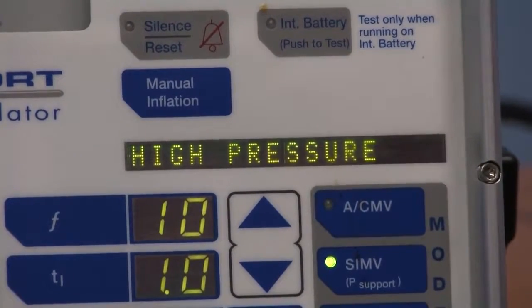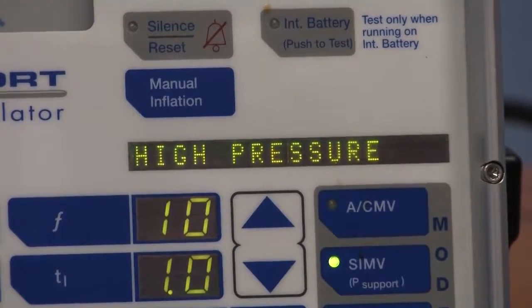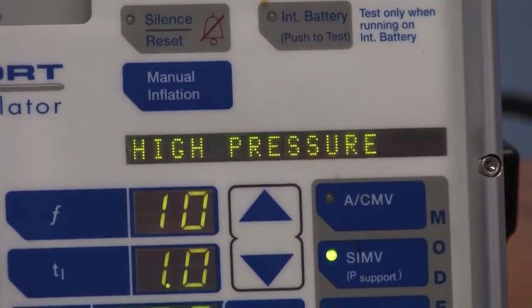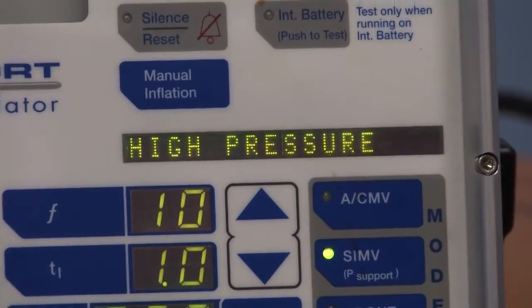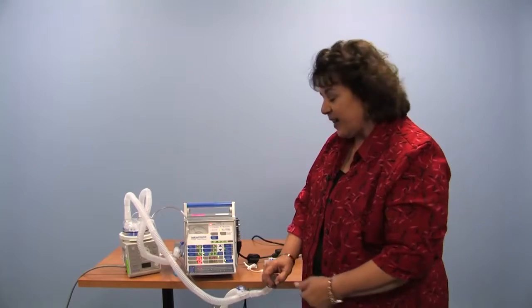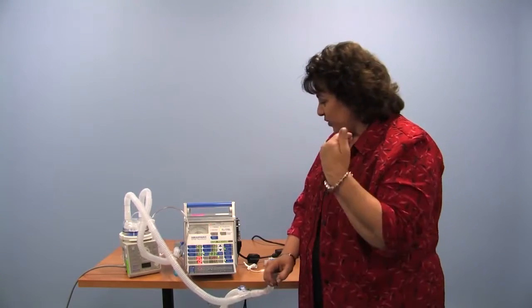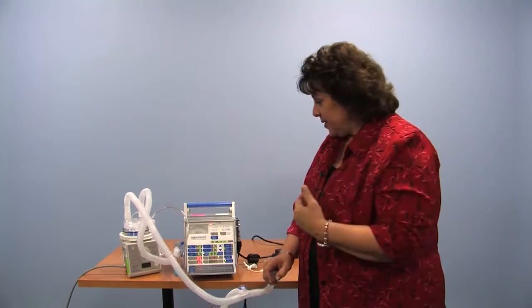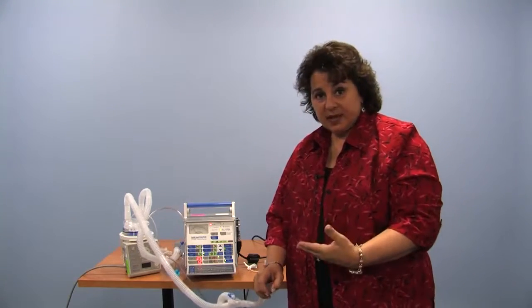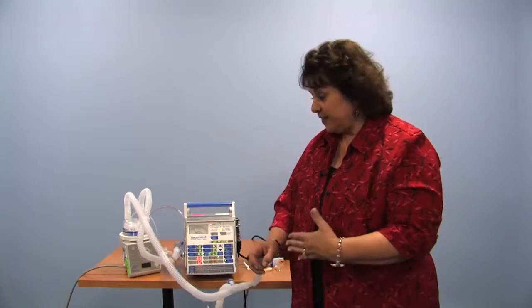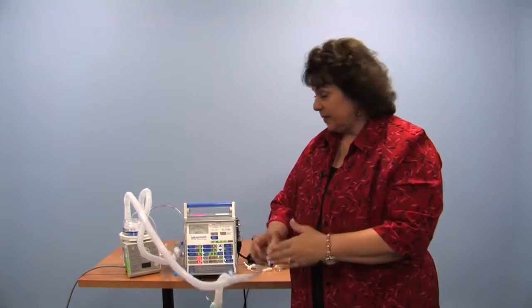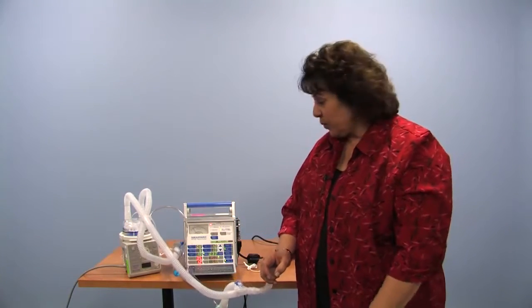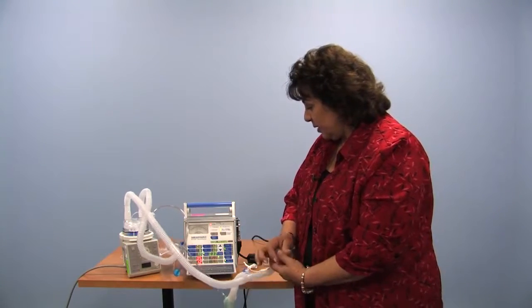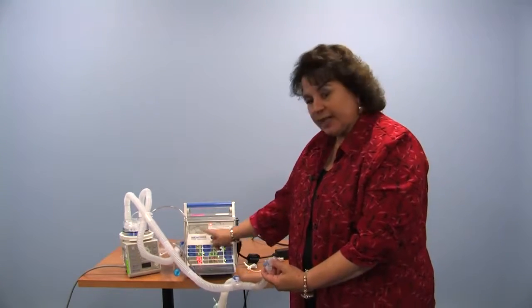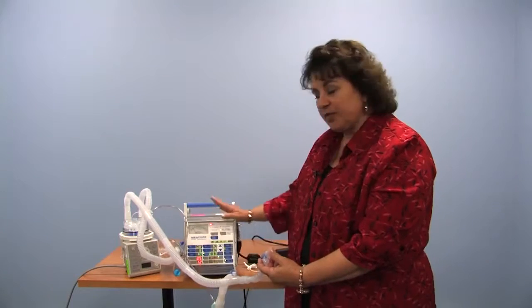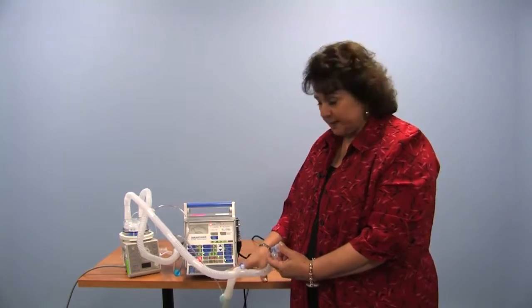What if the trach tube is blocked? We see high pressure in the window. We see it popping off at the 35 we've asked it to, and we see the high pressure alarm illuminated. We also had an audible alarm. So this situation may reset because the child coughed and turned, but if in fact the circuit was plugged and the trach tube was plugged, when the machine tries to blow in the 300 cc's, it cannot, and this alarm is going to continuously go off until you address it.